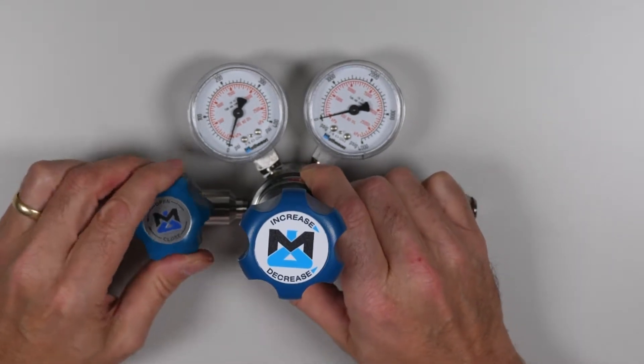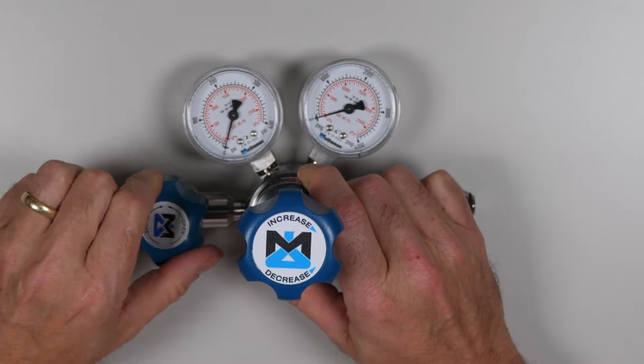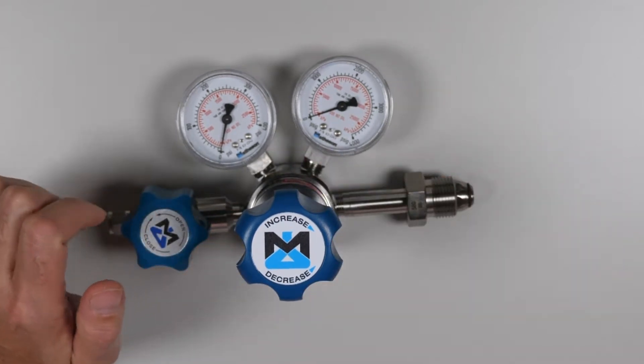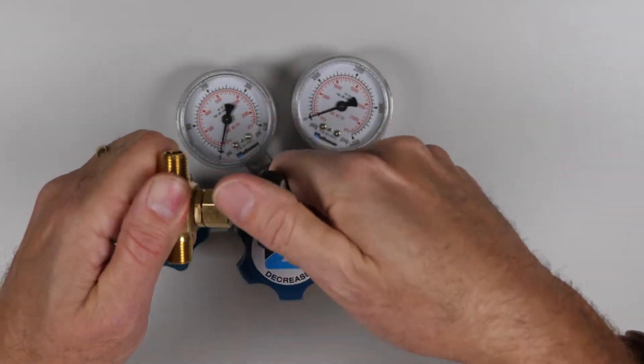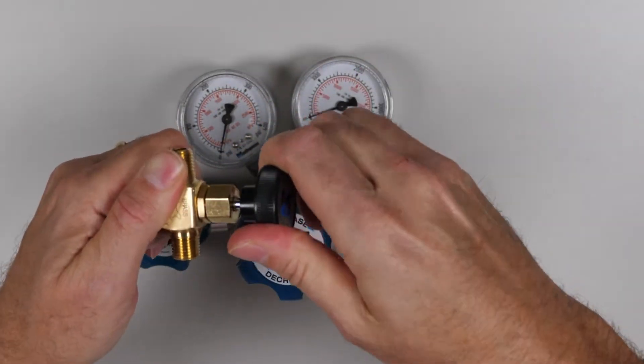Many of our regulators have full-turned diaphragm valves. Some regulators have a multi-turned needle valve which offers better flow control over a full-turned diaphragm valve.